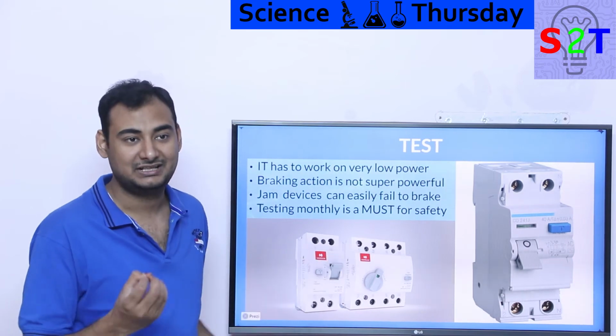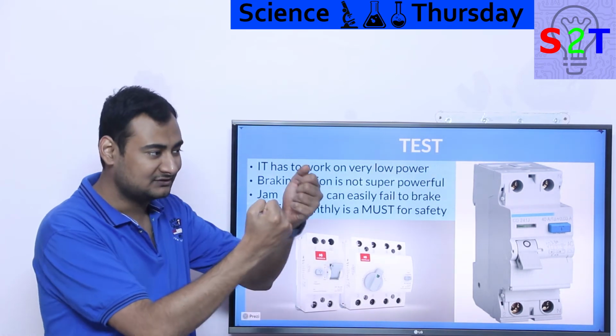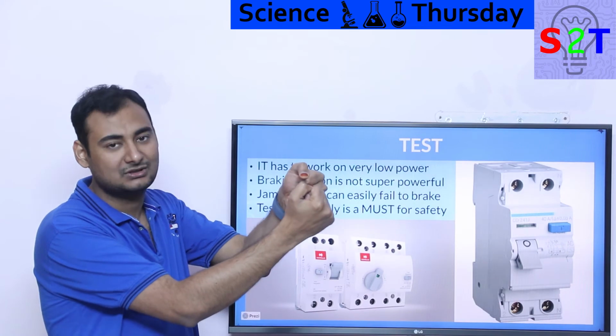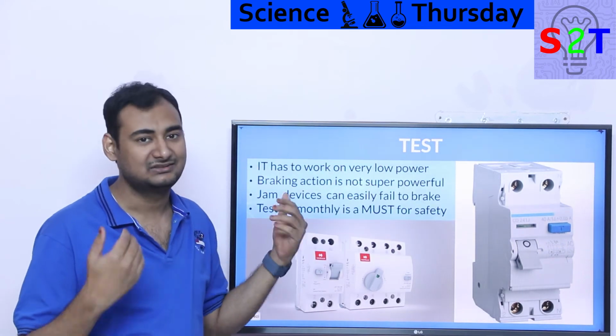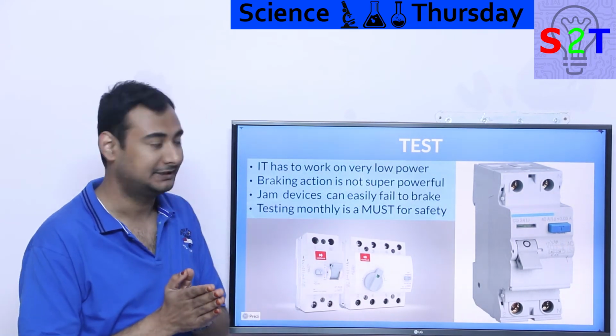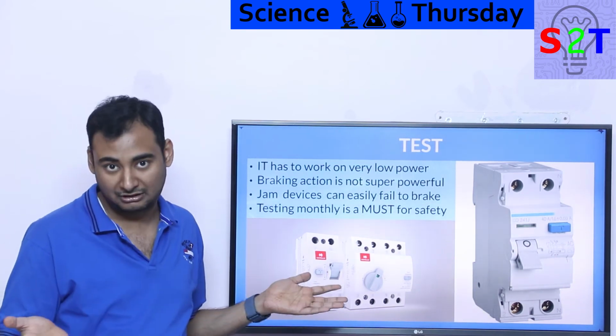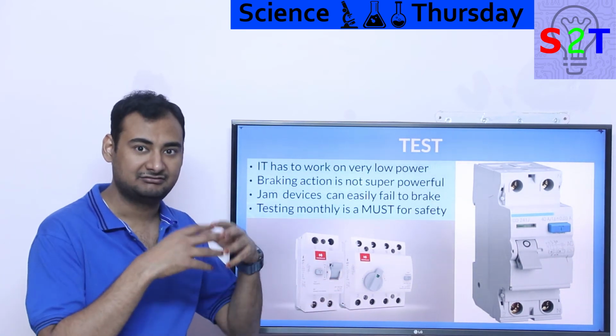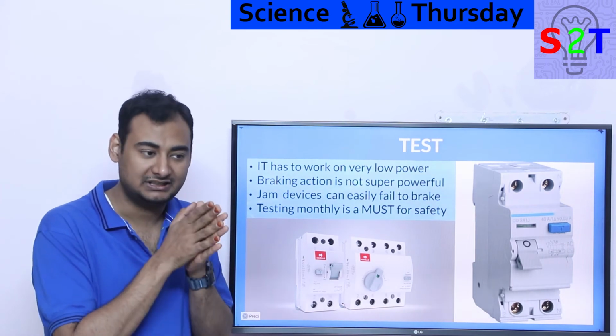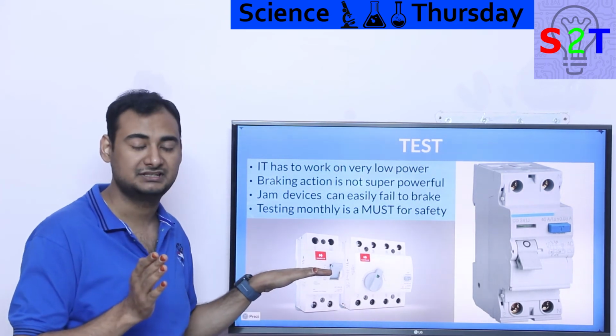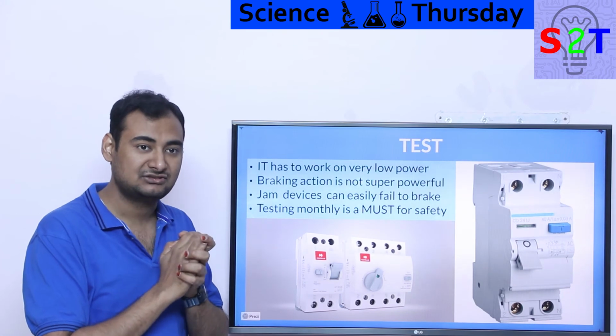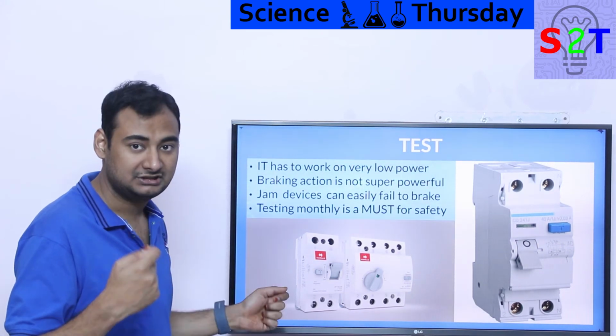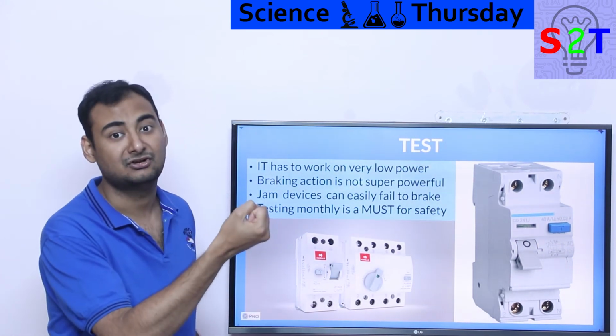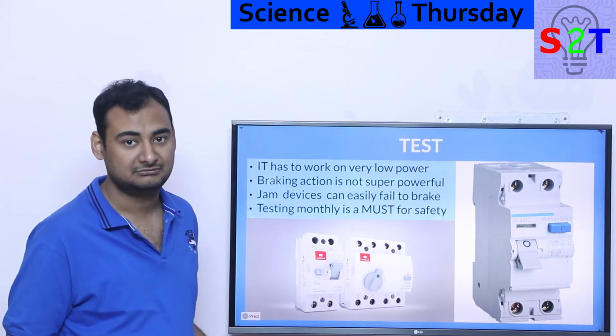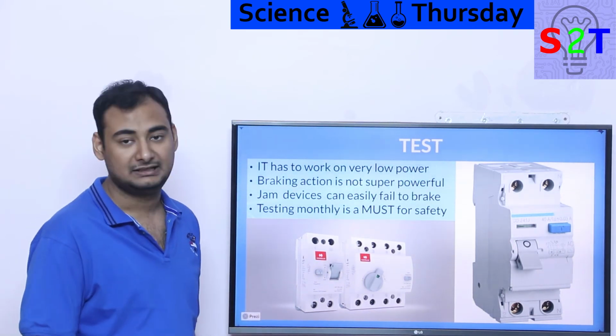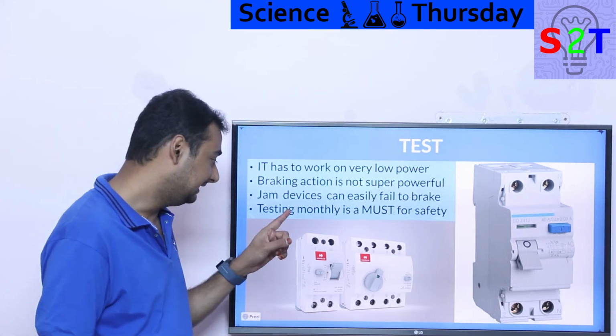This puppy on the other hand barely has anything. It barely has a spring which barely holds on a system that has to work on 30 milliamp. So power wise, it's not that powerful. So inherently it's a sensitive equipment. Now what will happen, let's say you are talking about a kitchen, you have grease in the air, you have a scenario where things will get onto the plunger side of this thing, and jam it up. And because it does not have huge amounts of power, it will detect a fault, it will trigger the system, but the plunger will simply not disconnect because it got jammed. It does not have enough energy to do its job, and now you are getting electrocuted. So fundamentally it has to have a test button.